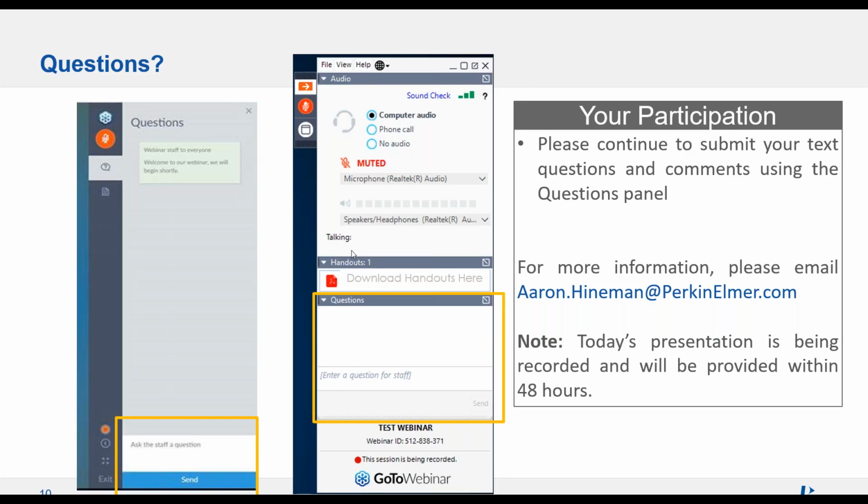Yeah, so the continuation after that question was a statement. Essentially, we've tried to look for low levels of cadmium and lead in baby food, and we keep seeing that the calculated concentration comes back as negative in the report. Well, for me, a negative in the report can be a couple of things. It can be the calibration bias. It could be your blank. It could be higher concentration than your actual samples.